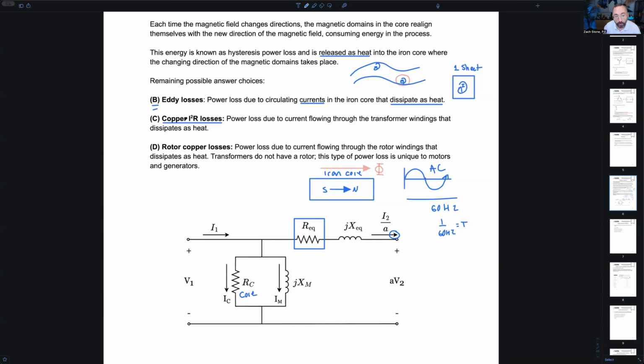Why are these I squared? Why is it called copper losses? Well, that's the copper conductors wound into the transformer winding. Why is it called I squared R losses? If I wanted to calculate the power dissipated, I'll call it PCU for P copper. How would I calculate the power dissipated in that resistor, which gives us the copper losses? It would give us the I squared R power losses. What formula do we use? We use the formula for real power P in watts from current and resistance: I squared times R. That's the I squared R losses.